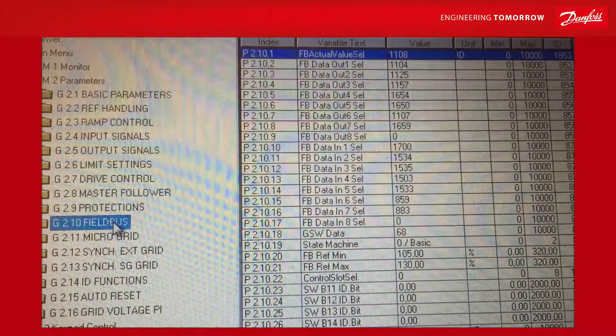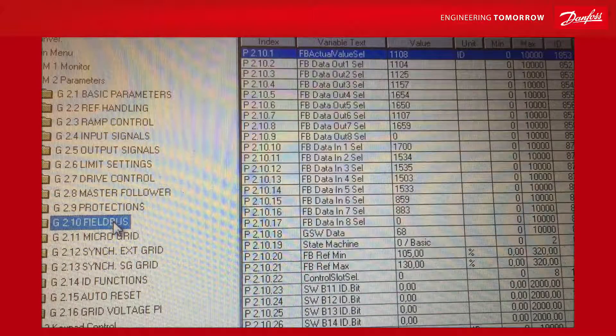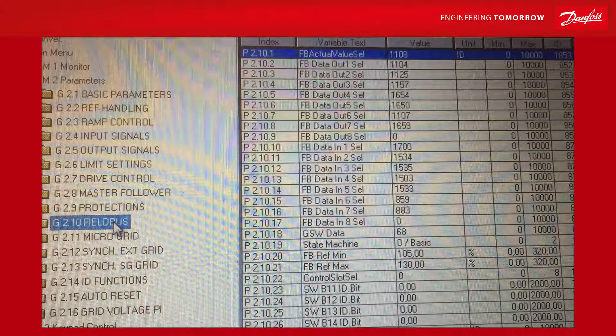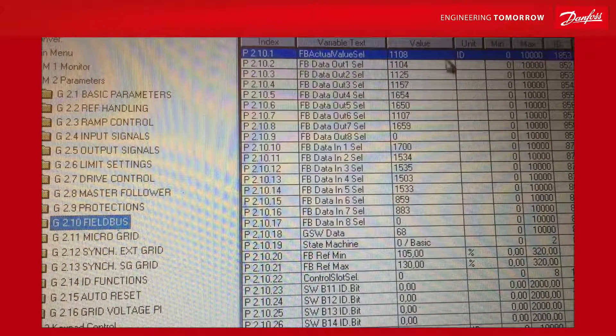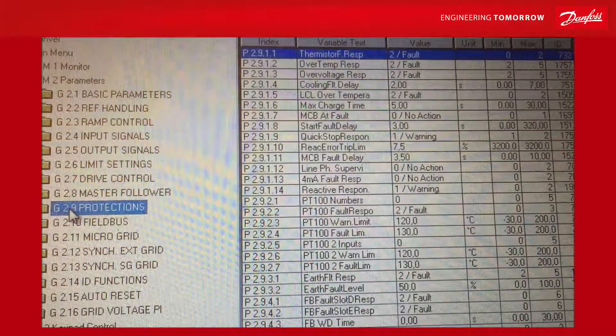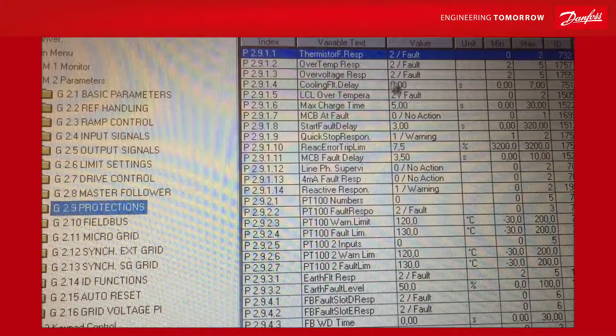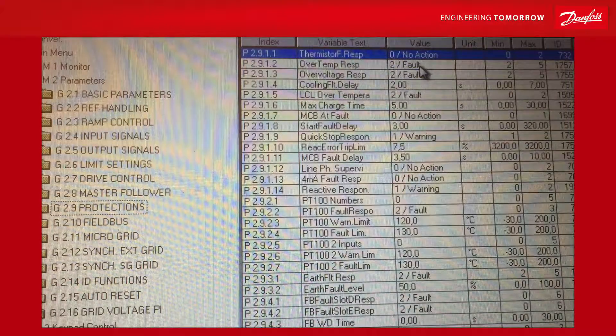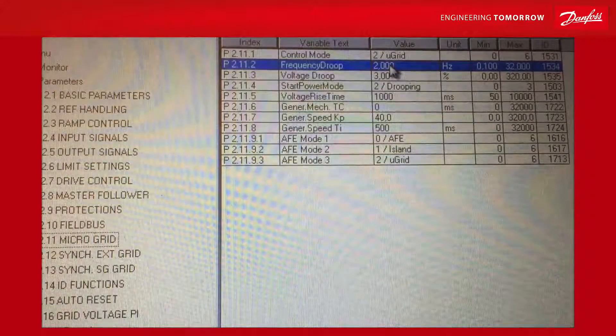For the field bus, I will put in the ID numbers so that my screen will show what is going on in the process — I copy this from a previous project. In the chapter for protections, I turn off the thermistor fault response because I do not have a thermistor, so I set it to no action.